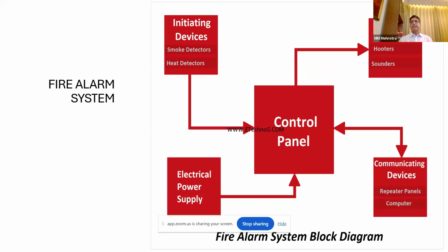This is the basic scheme of how this thing works. It means there are detectors which will give signal to control panel. Control panel is also getting electric power supply. This is normally LT supply, 120 volt or 240 volt. Then there are hooters and sounders, which it will activate, and there are communicating devices at the manned location, repeater panel or computer screen.